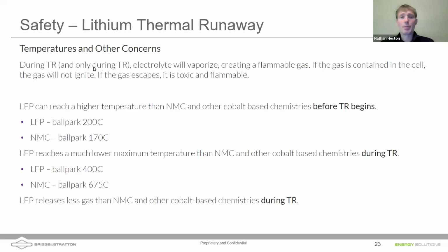So a couple other things to point out about safety. When thermal runaway begins, an LFP battery has to get to a couple hundred Celsius before that even begins, on the order of 300 Fahrenheit or so. An NMC battery can go into thermal runaway at a lower temperature, around 170 Celsius. That difference matters, it determines the likelihood that your battery might go into an off-gassing event.